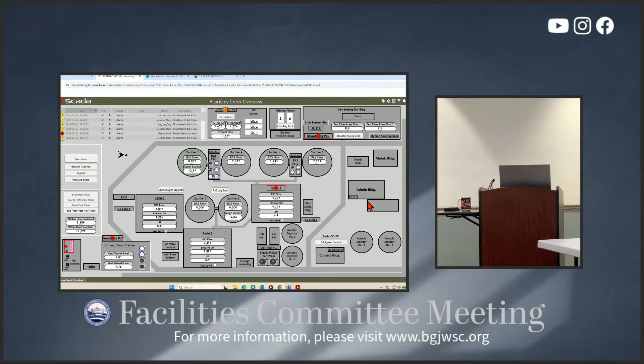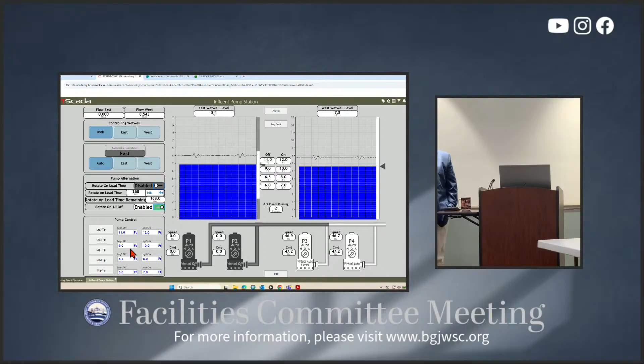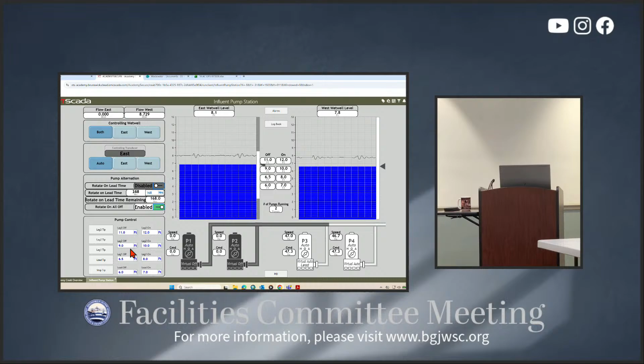So if I click on the influent pumping station here, it's going to bring up another screen. And we get more information about the influent level. So it tells you how many pumps are running, which 2 pumps are running, the speed that the VFD is telling them they need to be running, and it gives you a graphical representation of what the level is in that tank at any one point. Now, our goal is for that to be a perfectly straight line. Flow is not 100% consistent, so it never is a perfectly straight line. But that's pretty good consistency. You're feeding about the same amount to your plant all day long at that rate.